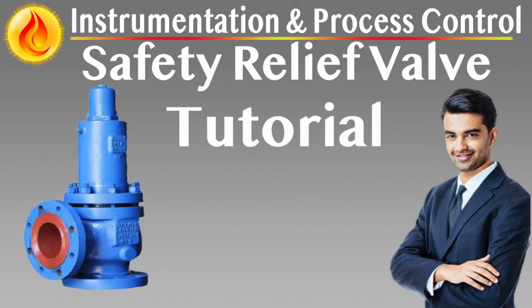Operational constraints and considerations. Not suitable for dirty or fouling services where pilot ports or sensing lines may clog. Instrument air or control power may be needed for some configurations, e.g., air reset or remote venting. Vibration-sensitive installations may require secure mounting or flexible sensing line supports. In case of pilot or sensing line failure, ensure the main valve still opens under maximum pressure conditions.